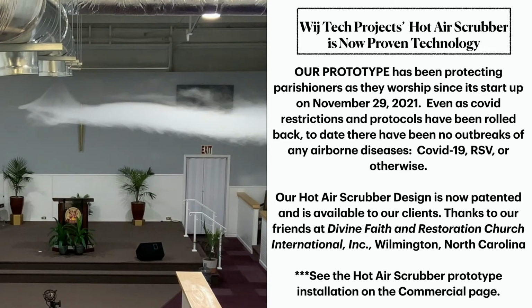Here's another view of the smoke bomb after it's finished burning. You can see that we clearly have established what we want to see, called stratification. And you can see that the nozzles are doing their job. They're collecting the smoke. This system was installed in a church sanctuary in November 2021. It's been running since then.